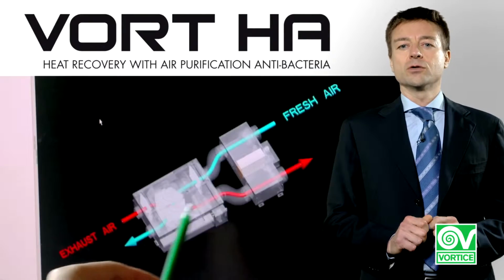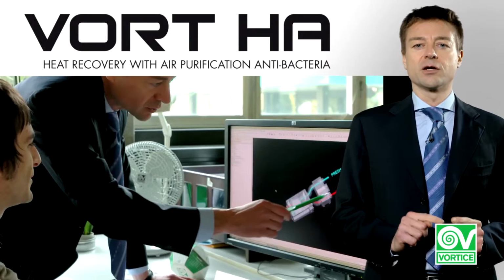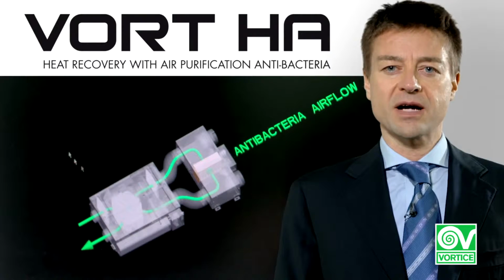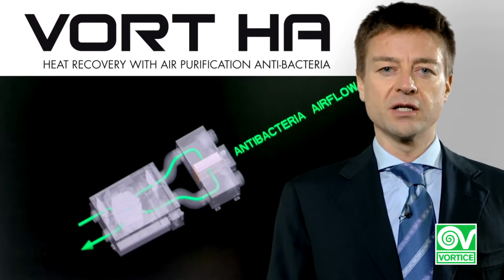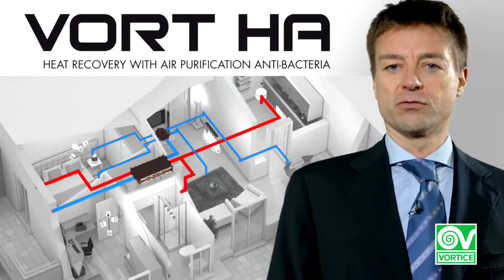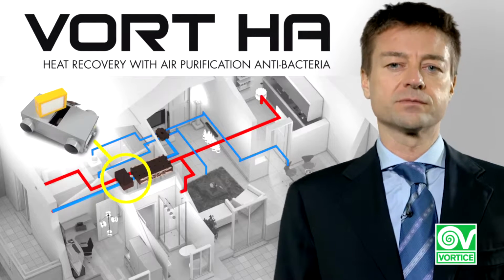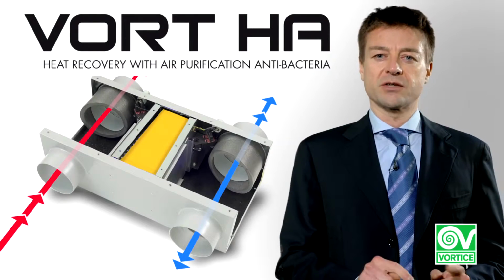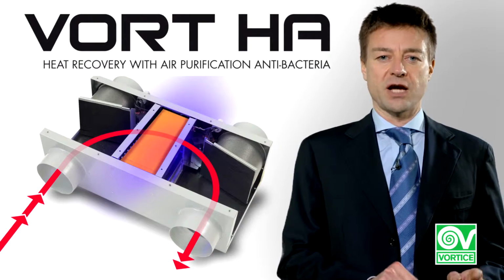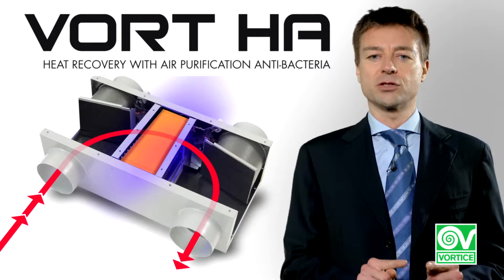Vortice are now presenting VORT-HA, a controlled cross-flow mechanical ventilation system integrating antibacterial treatment with normal heat recovery ventilation using supply air from outside. The HA system, heat recovery with antibacterial, basically includes two elements: a VORT heat recovery unit and a filtering unit with antibacterial properties. When activated with specific valves, the outgoing flow of air is blocked and diverted towards a special antibacterial filter, treated with chitosan and titanium dioxide-based solution.